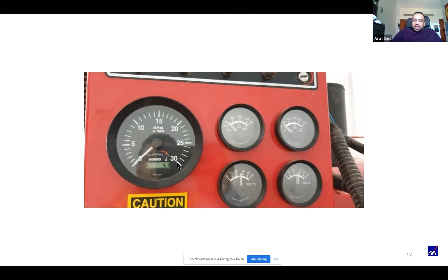So this is something that I see very often because the current requirement is for approved contractors to do maintenance on these fire pumps quarterly. And what I have seen as a market practice, in a few of the places that I've been to, is that they literally start the fire pump, they switch it off, and hence why it takes 8 years to achieve a paltry 4 hours of runtime.